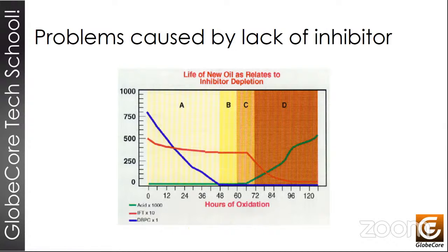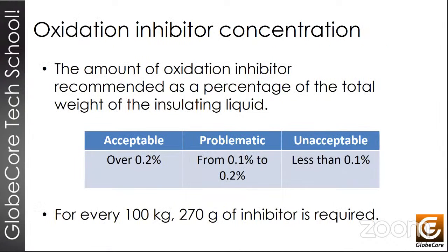Right, next slide, please. The best content for inhibitor, the concentration is somewhere between 0.2 and 0.3%. Anything less than 0.1% is not acceptable. It's very important to understand that this number refers not to volume, but to weight, mass. And also keep in mind, density of oil is 0.87. That tells us that every 100 liters of dielectric oil has an approximate weight of 87 kilograms. So we will need not 300 grams, but only 270 grams of inhibitor for every 100 kilogram of oil.